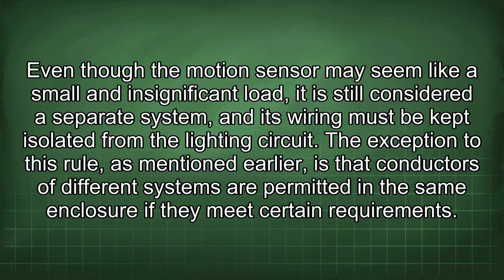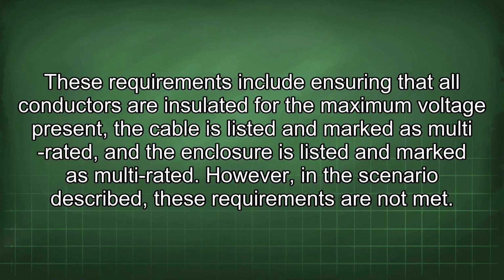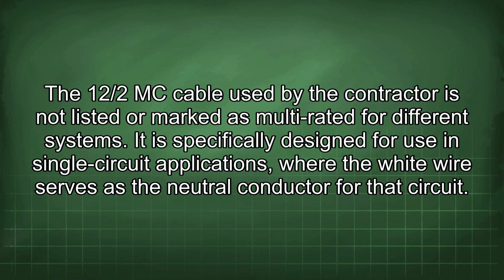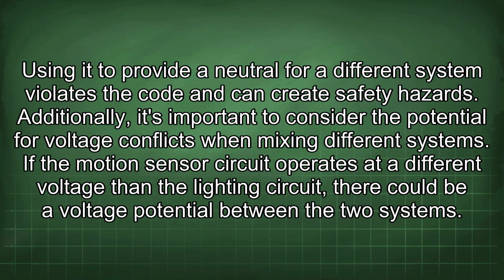The exception to this rule, as mentioned earlier, is that conductors of different systems are permitted in the same enclosure if they meet certain requirements. These requirements include ensuring that all conductors are insulated for the maximum voltage present, the cable is listed and marked as multi-rated, and the enclosure is listed and marked as multi-rated. However, in the scenario described, these requirements are not met. The 12/2 MC cable used by the contractor is not listed or marked as multi-rated for different systems. It is specifically designed for use in single-circuit applications where the white wire serves as the neutral conductor for that circuit. Using it to provide a neutral for a different system violates the code and can create safety hazards.